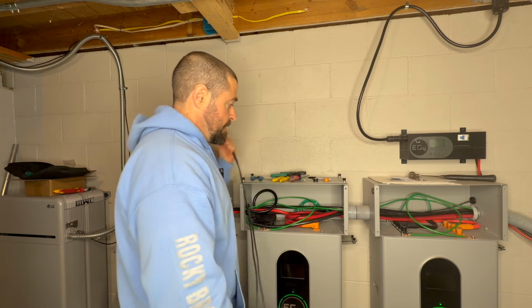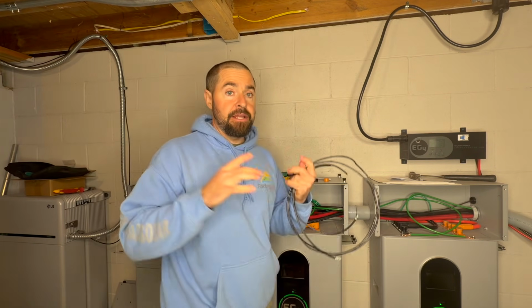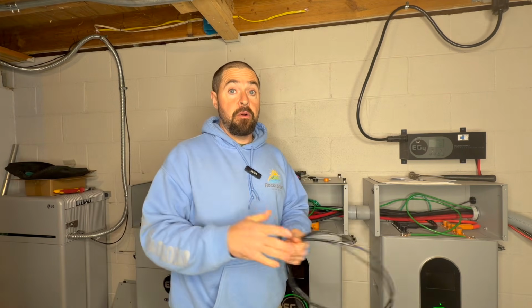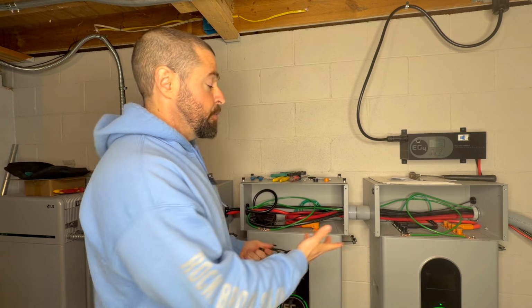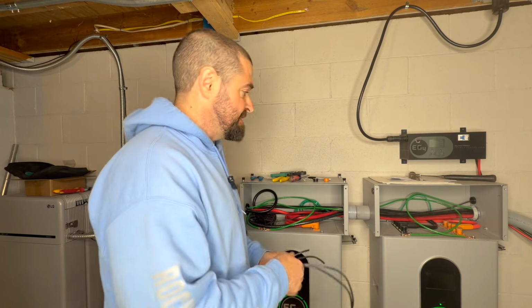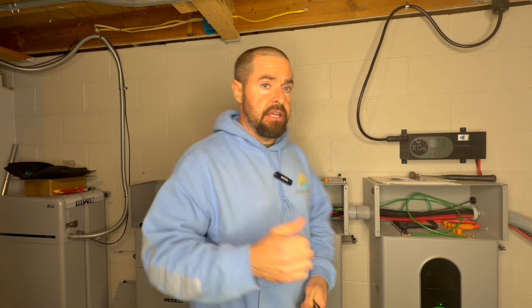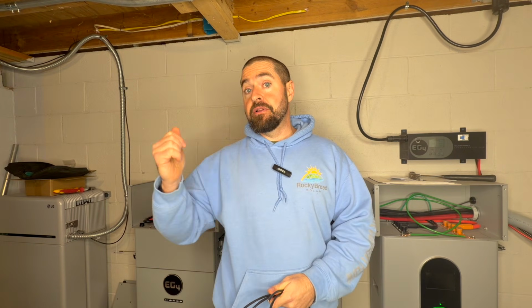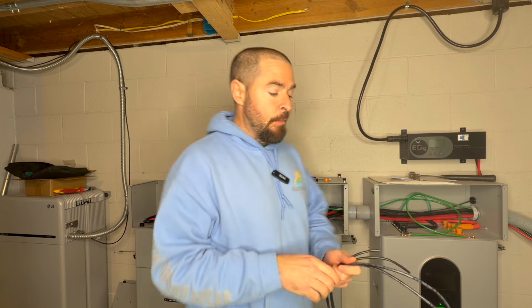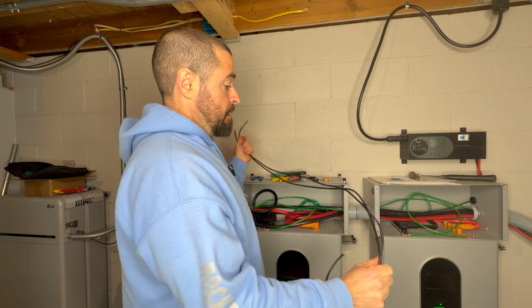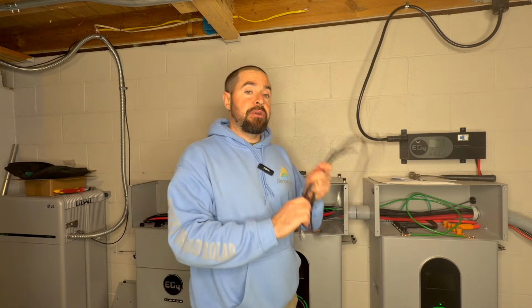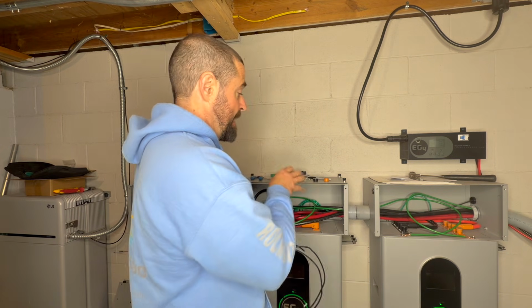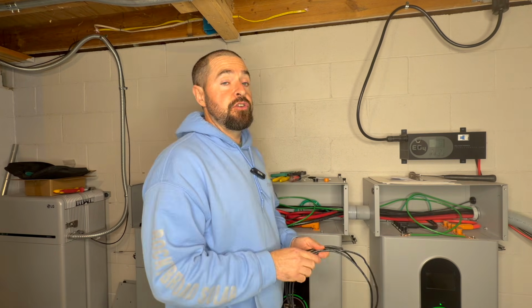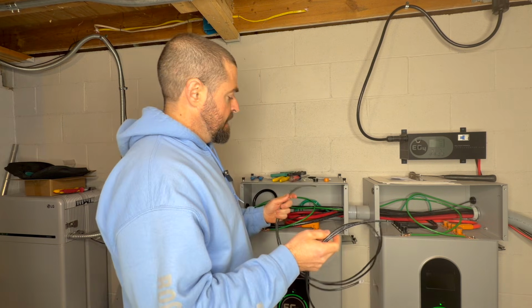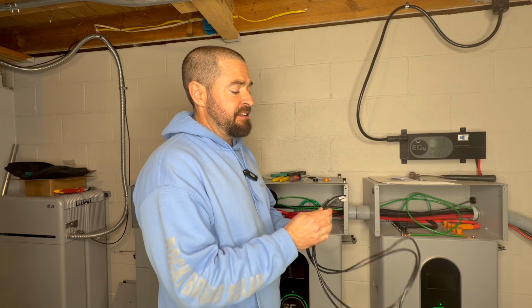A few things to note when paralleling a 314 amp hour wall mount battery with existing 280 amp hour wall mount batteries. You need to make the 314 amp hour battery the leader, and the communication cables between the 314 and the 280s, and between the two 280s, are special cables.